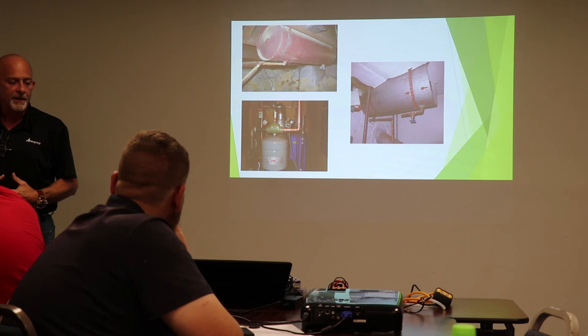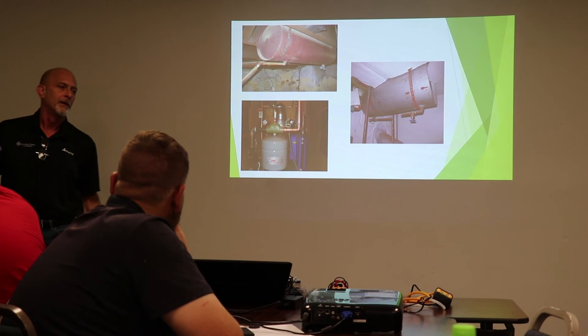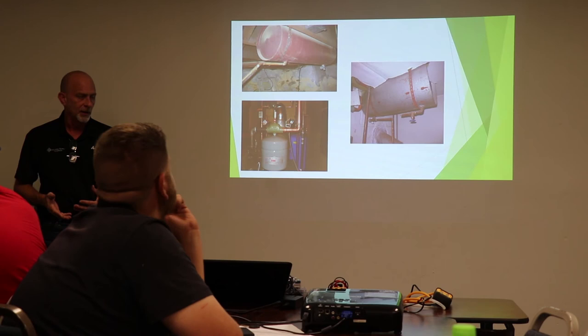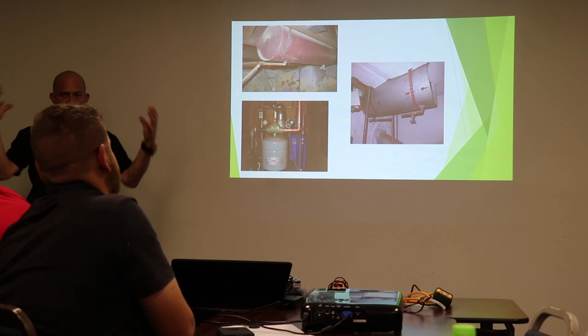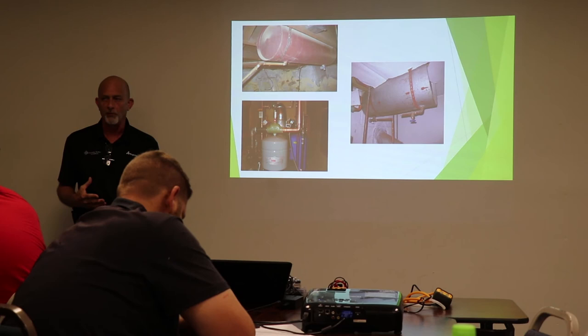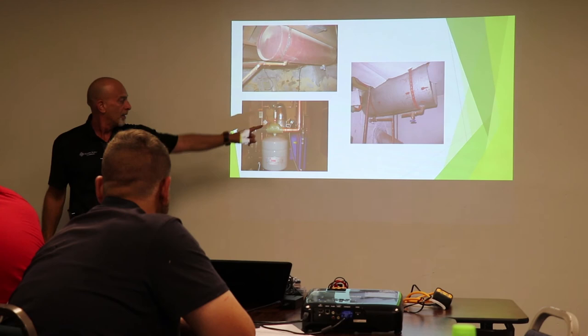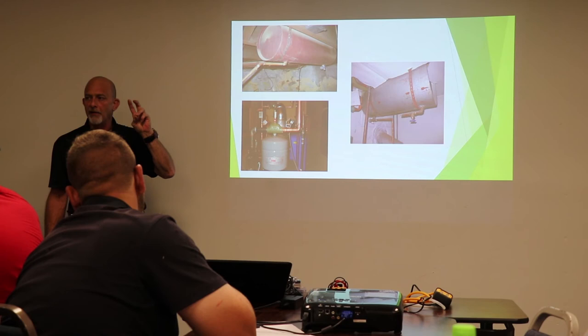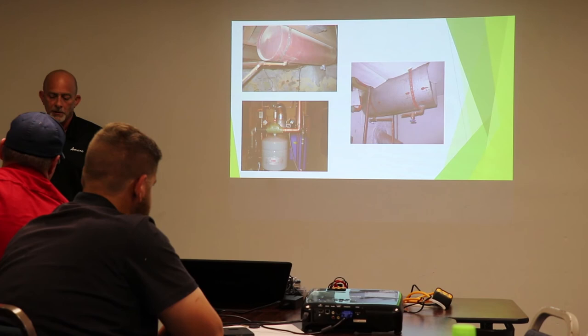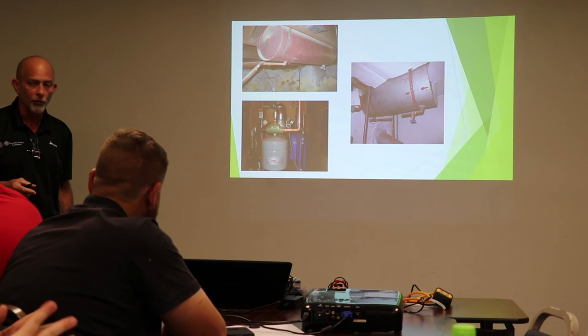Even though a water boiler is a sealed system, you will still have to add water to it periodically. We're heating water up, it's cooling down, expanding, contracting. We do have natural evaporation going on in a water boiler. We always have to add more water, but it's minimal. With that in mind, you'll never have a problem because that minimal amount of air that's introduced to the system as it goes around, it's automatically taken out. Now, if you fire that system up and you hit the pumps on, you hear a gurgle, you got air in there. Start bleeding.